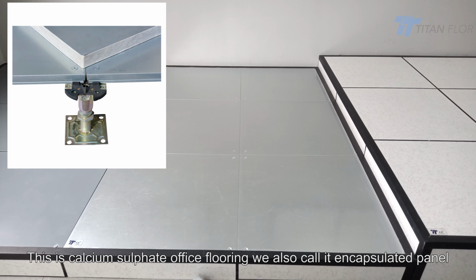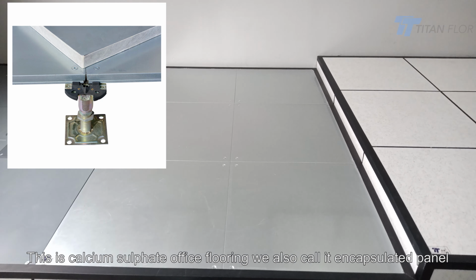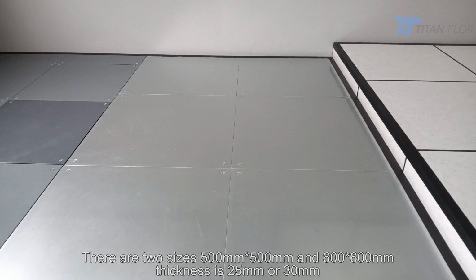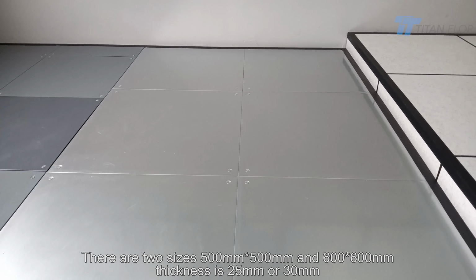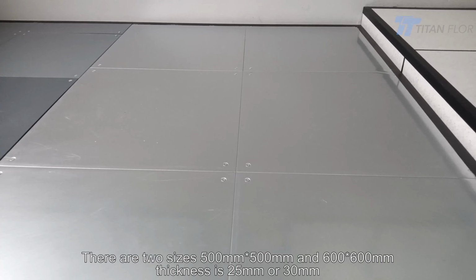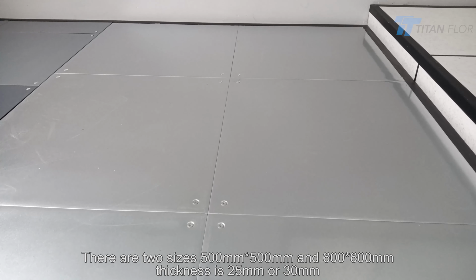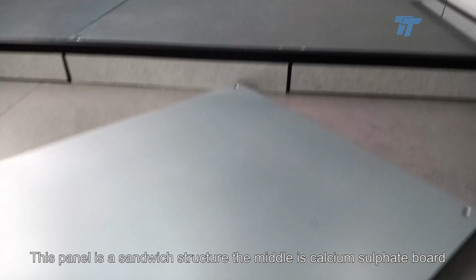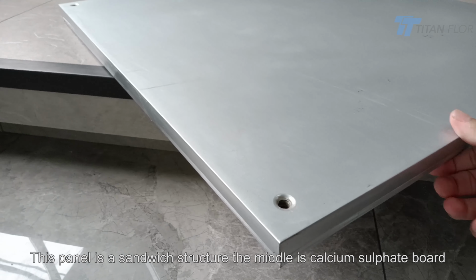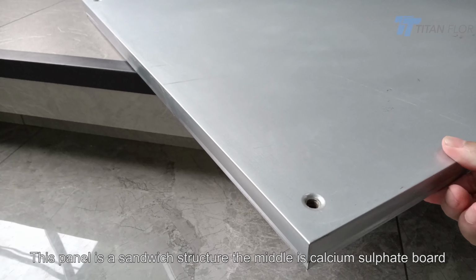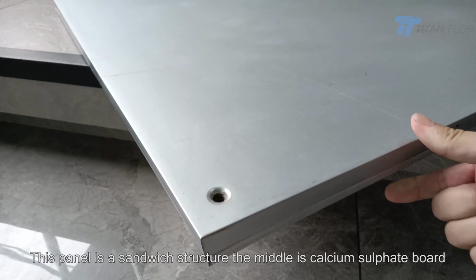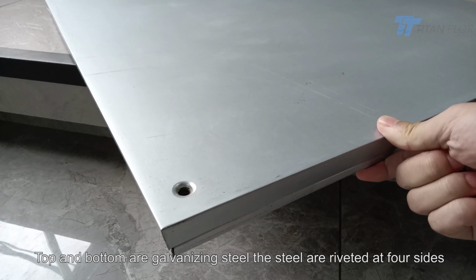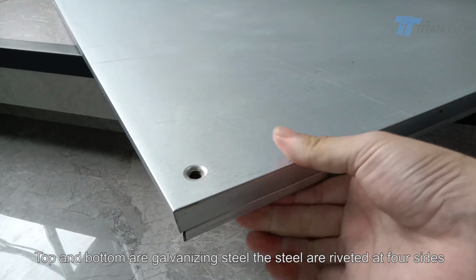This is calcium sulphate office flooring. We also call it encapsulated panel. There are two sizes, 500 and 600 mm. Thickness is 25 or 30 mm. This panel is a sandwich structure. The middle is calcium sulphate board. Top and bottom are galvanizing steel, and the steel is riveted at the four sides.